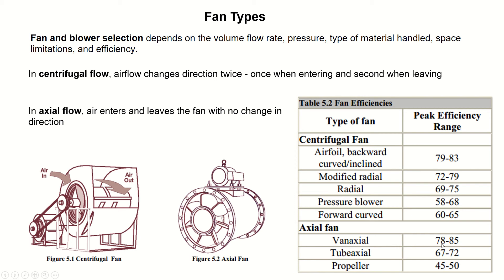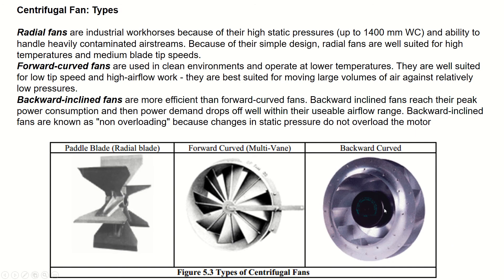There are three major types of centrifugal fans. Number one is radial fans. Radial fans are used as industrial workhorses because of their high static pressures and ability to handle heavily contaminated airstreams. Because of their simple design, radial fans are well suited for high temperature and harsh contaminated conditions.